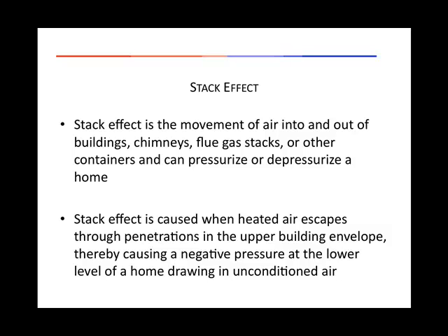Stack effect is the movement of air into and out of a building, chimney flue gas stacks, or other containers, and can pressurize or depressurize a home. Stack effect is caused when heated air escapes through penetrations in the upper building envelope, thereby causing a negative pressure at the lower level of a home, drawing in unconditioned air.